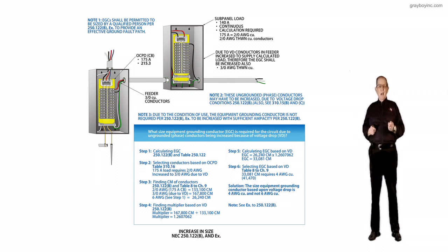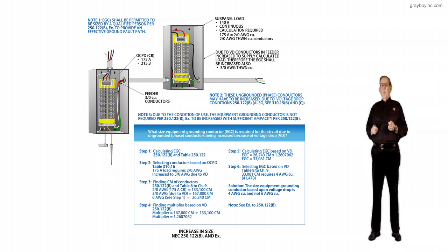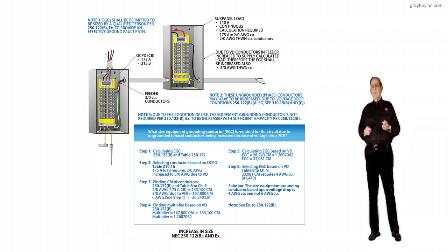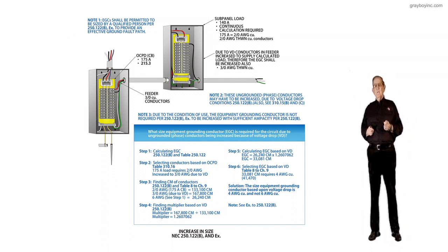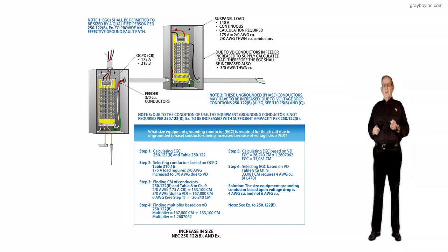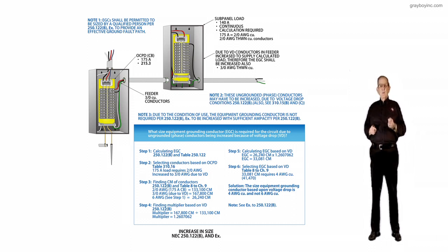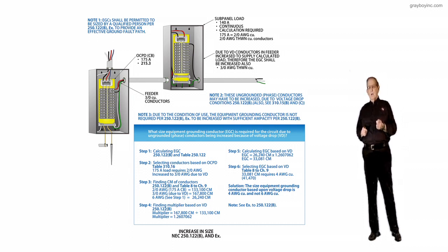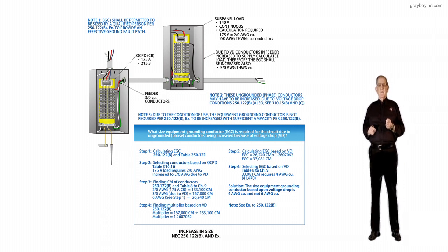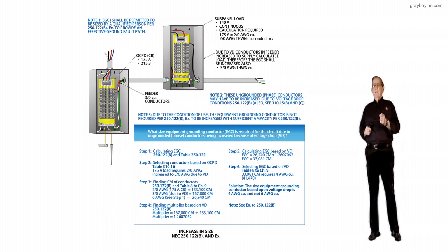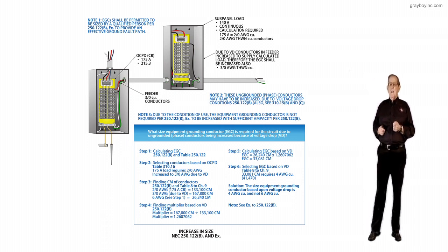If a wire type equipment grounding conductor is installed, the wire type equipment grounding conductor or conductors shall be increased in size proportionally to the increase of the circular mil rating of ungrounded conductors.